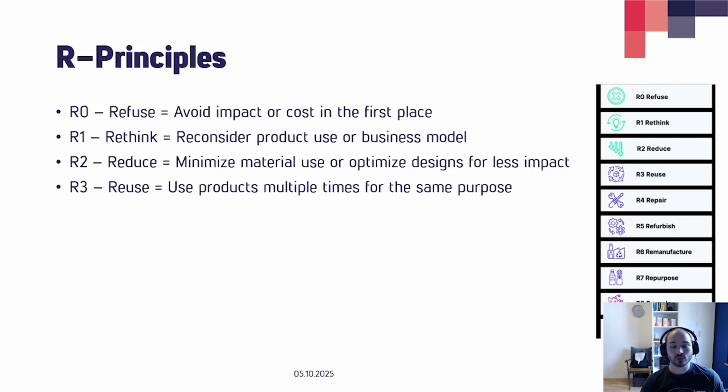Then reuse. You try to design your product for multiple uses with the same purpose without reprocessing. In MedTech, that is quite difficult to achieve because if you have a surgical device, you at least need to sterilize it in order to use it again for your application. And then a bunch of problems come in, such as logistics and convenience and stuff like that. So really think about how your reuse scenario will impact the workflow in a hospital, for example, or the workflow of a patient when it's a self-use device.